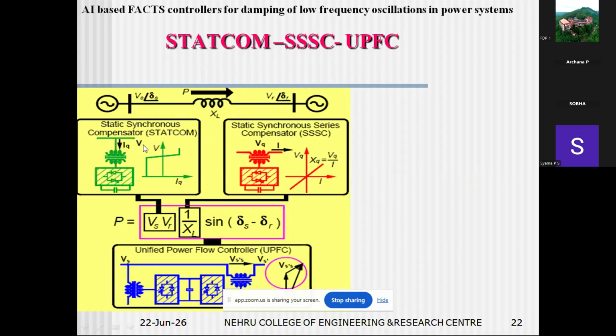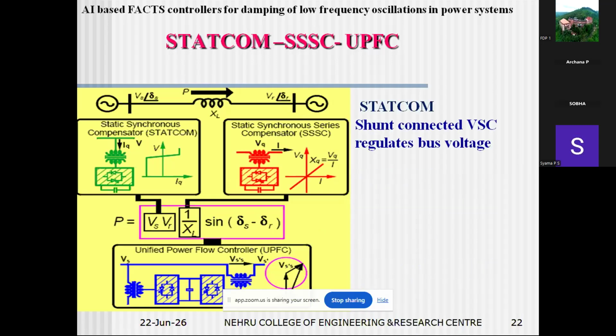Starting with the STATCOM: it is a shunt connected VSC that regulates the bus voltage. It is going to control the voltage, capable of changing this particular voltage, thereby the power flow can be controlled.